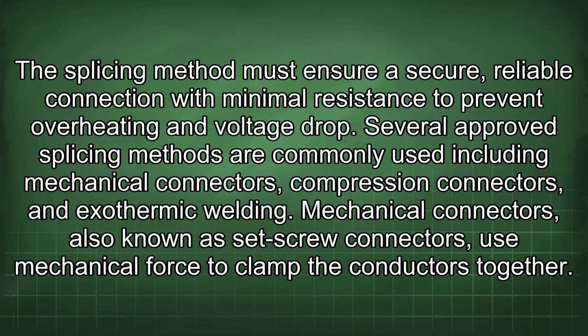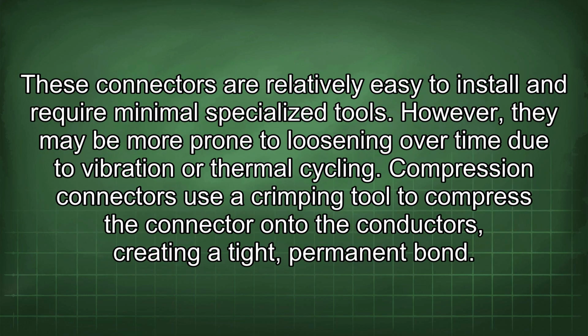Mechanical connectors, also known as set screw connectors, use mechanical force to clamp the conductors together. These connectors are relatively easy to install and require minimal specialized tools. However, they may be more prone to loosening over time due to vibration or thermal cycling.